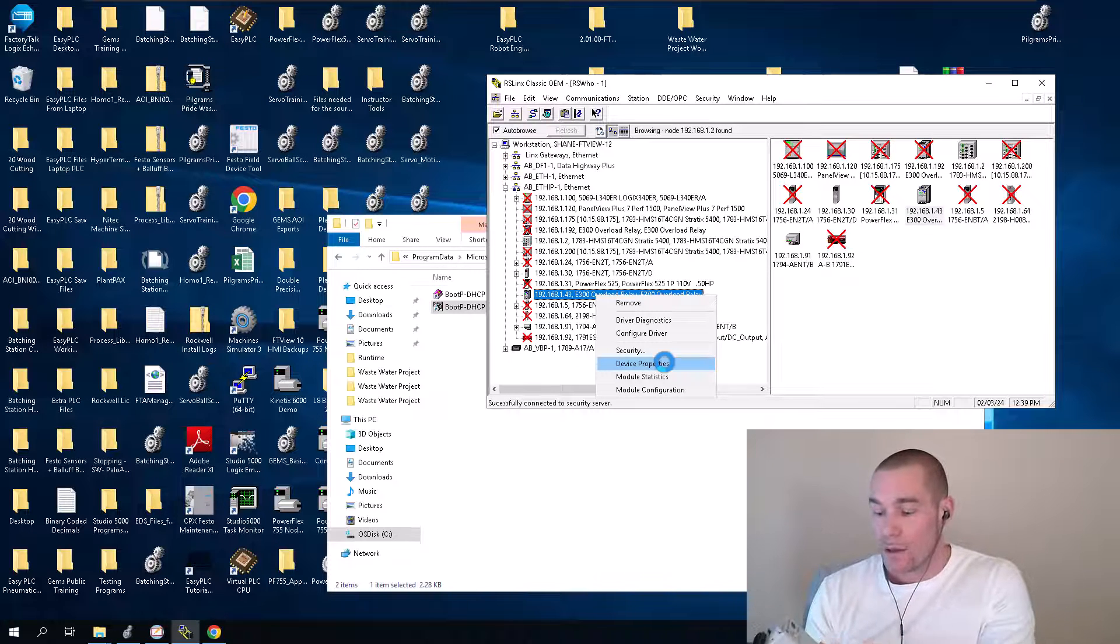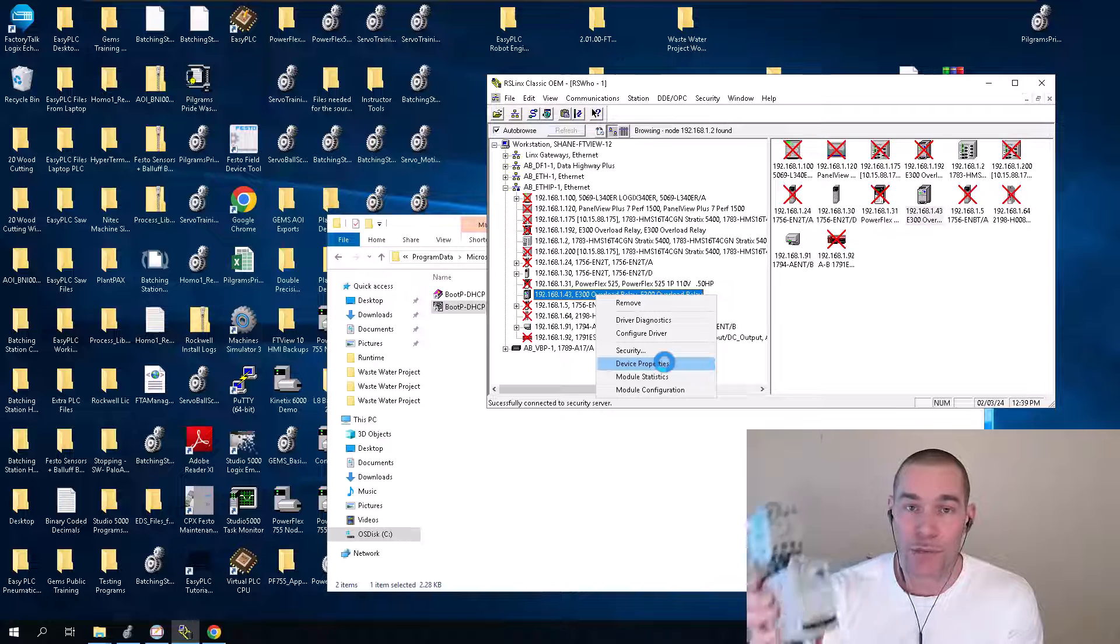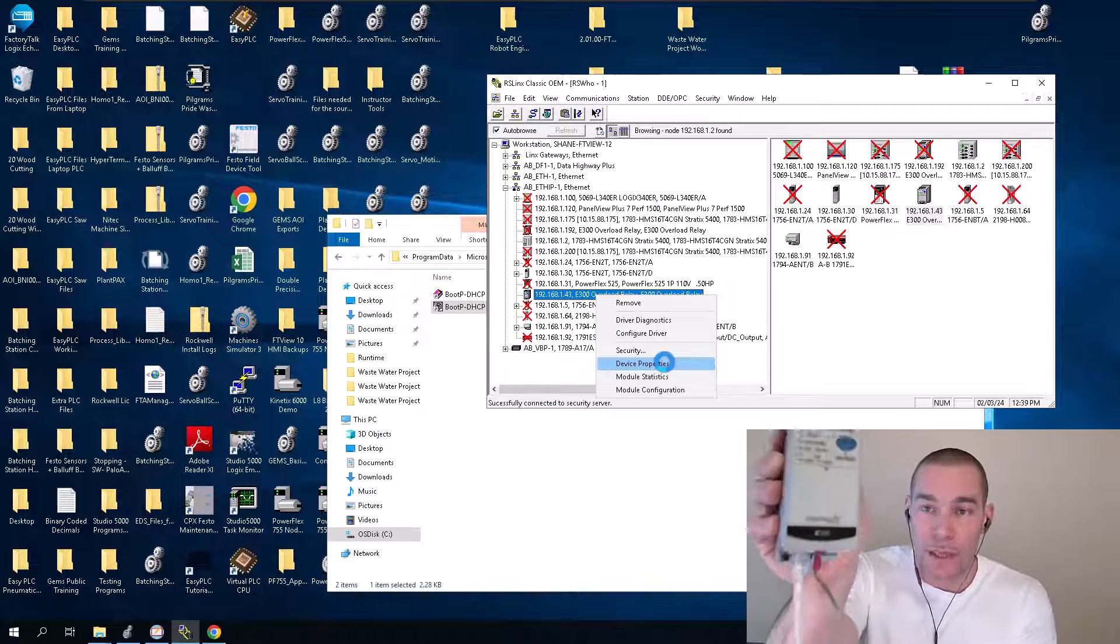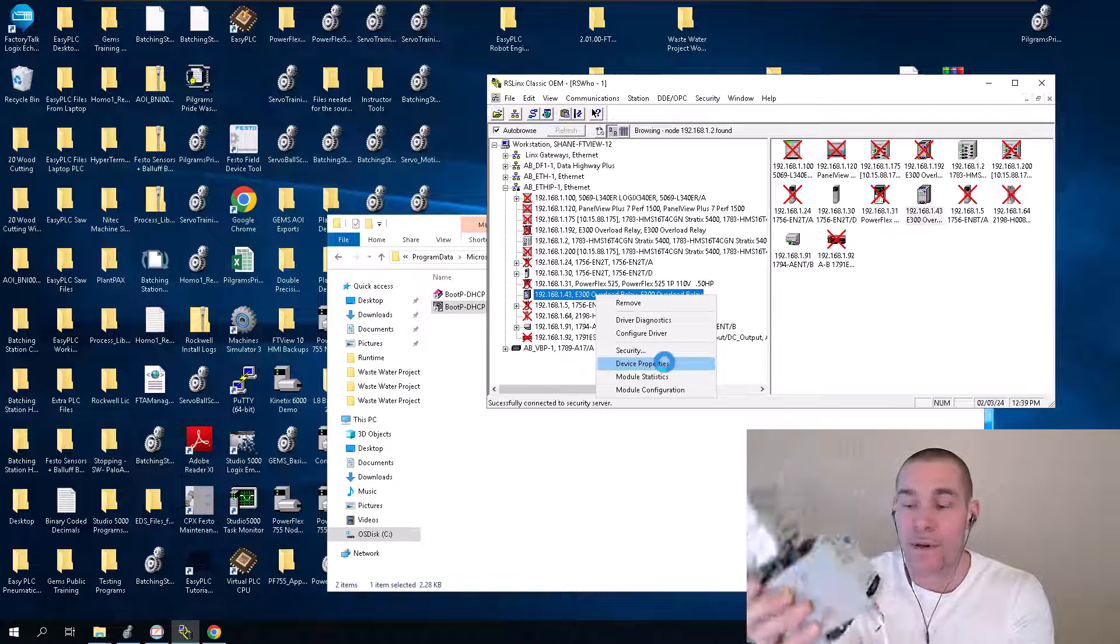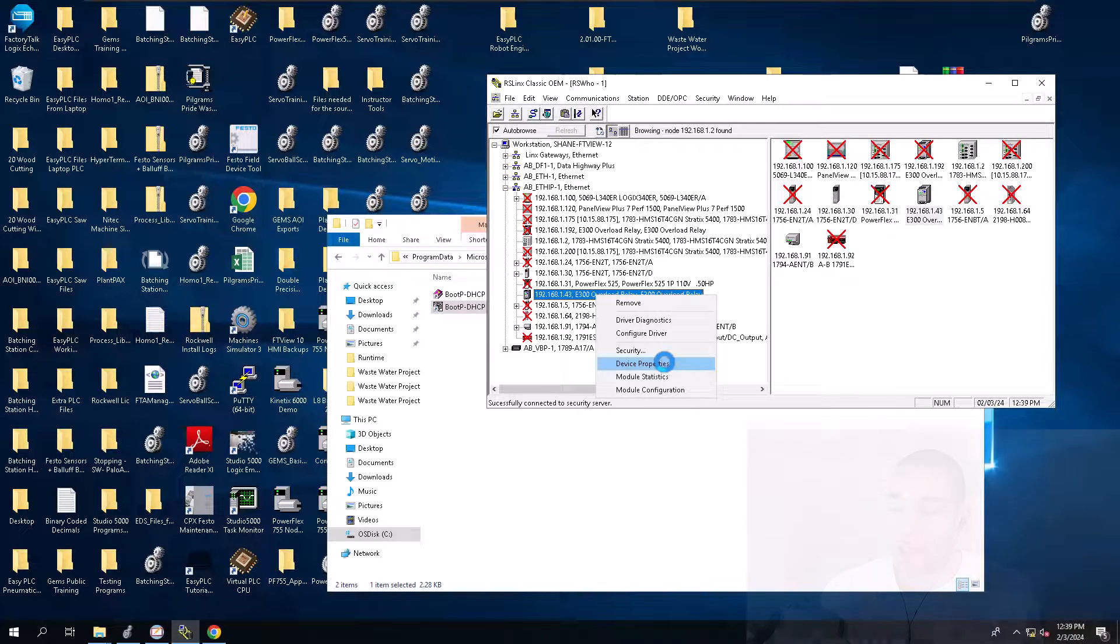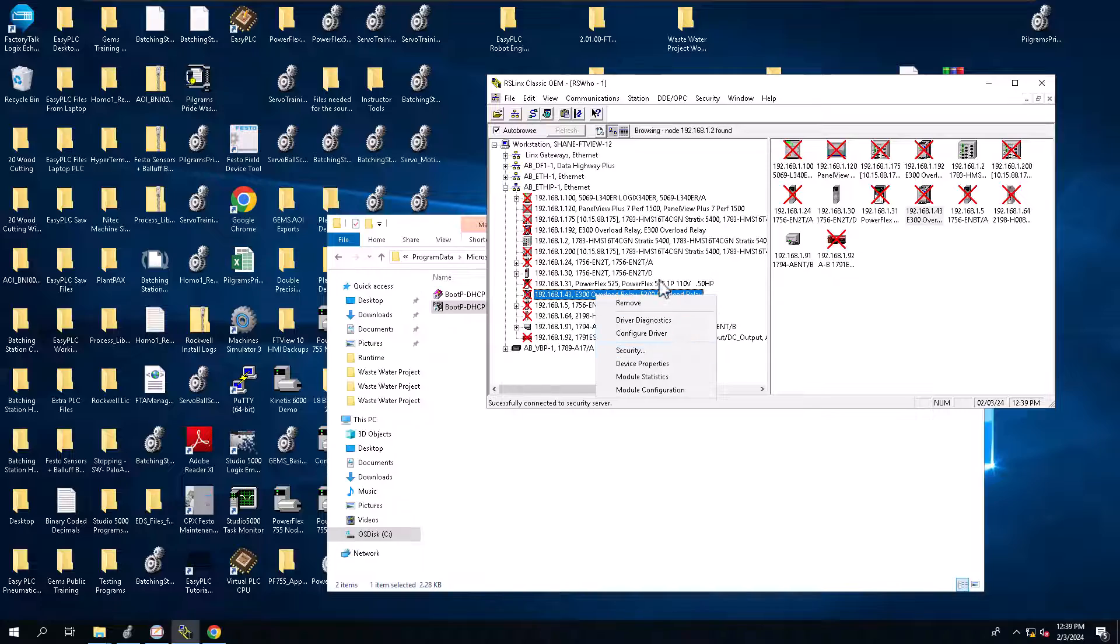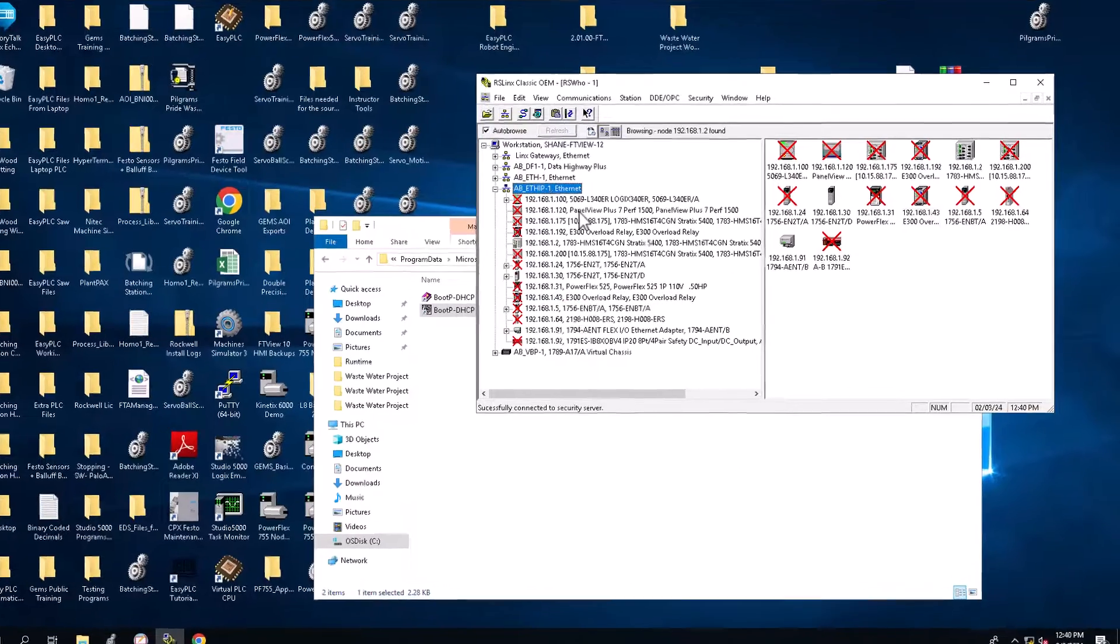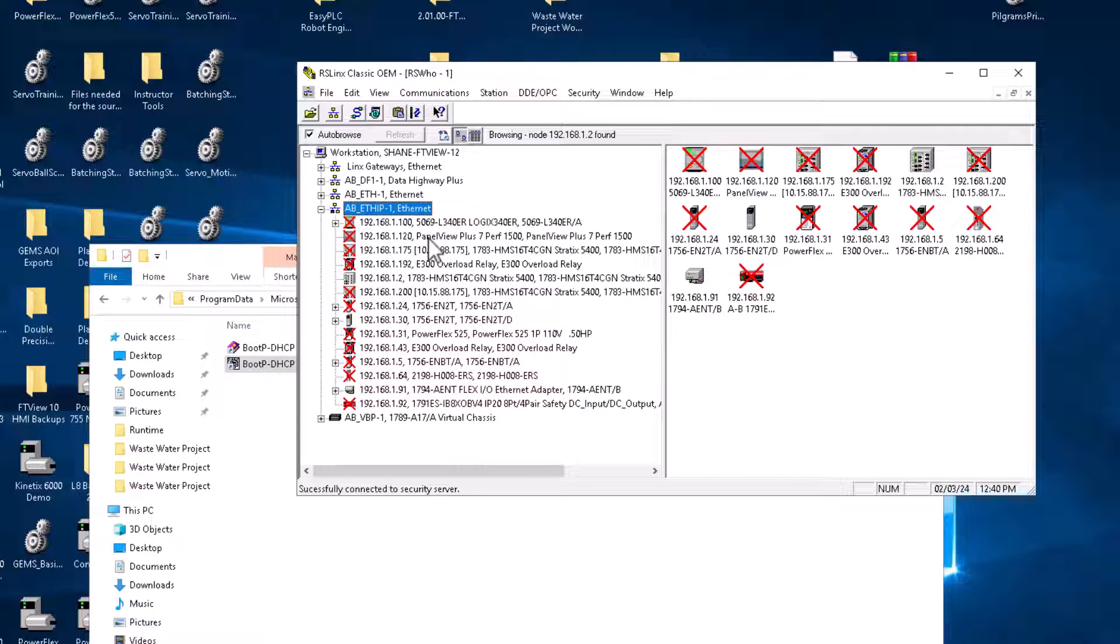I'm going to power cycle the actual E300. You have to power cycle every time you change the dip switches or else it will not take. It does take a second for this thing to power up. So just keep in mind and understand that this does take a second to actually power up.